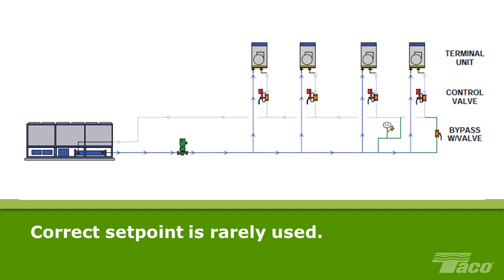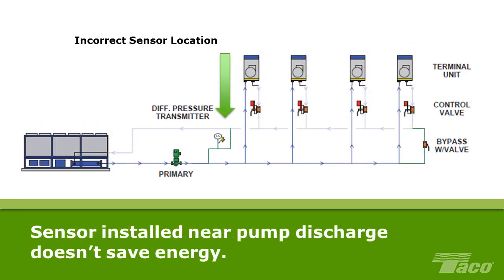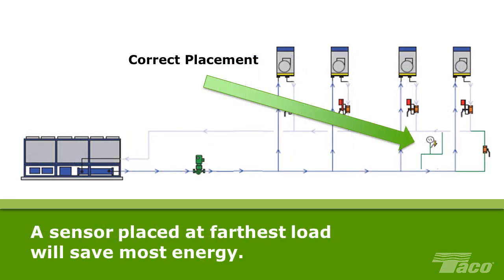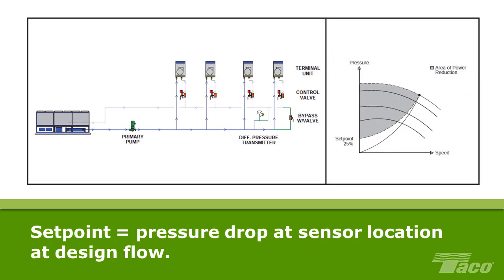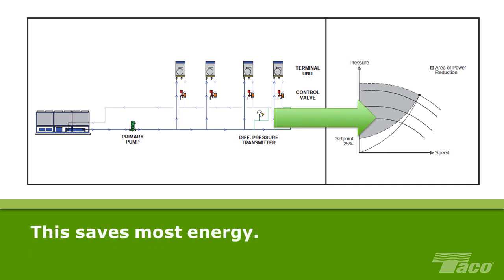Additionally, even when the sensor is correctly located in the system, a correct set point is rarely used. A differential pressure sensor located near the pump discharge won't save much energy. On the other hand, a differential pressure sensor placed at the farthest, most significant load will save the most energy. The set point must be equal to the pressure drop at the sensor location at design flow. The result is a significant savings in energy consumed.